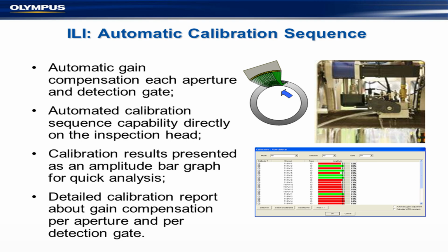We even have an automatic calibration sequence for this. You can see that we've got a sample up here. It runs over that little notch there, and it calibrates itself. This is a typical example of the printout. I presume the green is good and the red is bad. I never thought to ask that question, actually. And you pop out your amplitude, and it gives you the figures down there, and that gives you detailed and recorded values for your calibration.